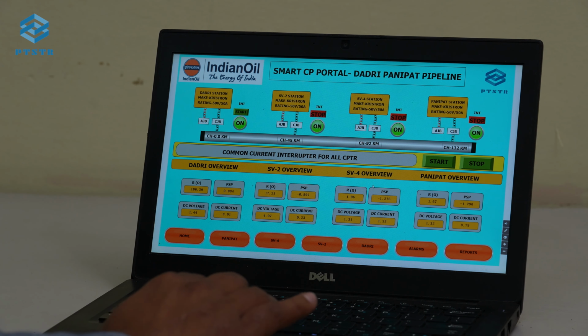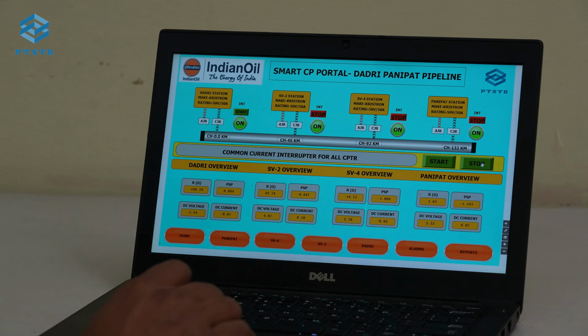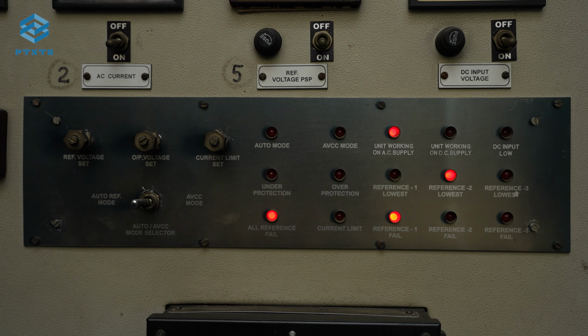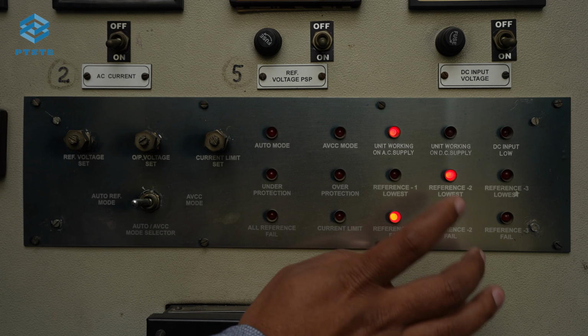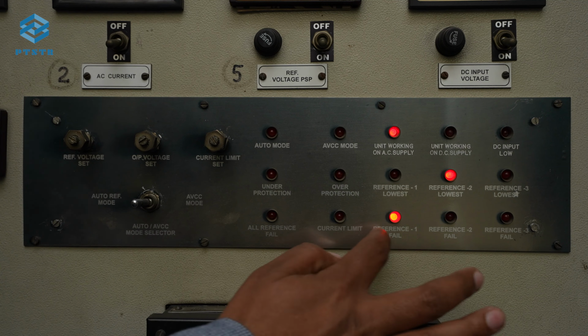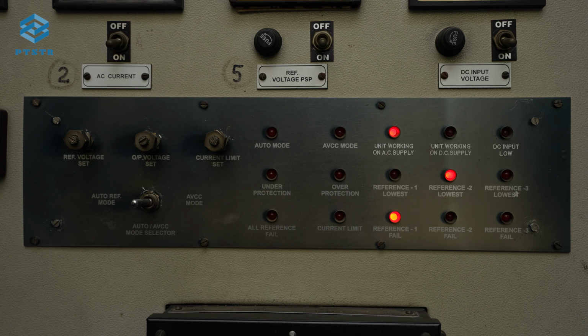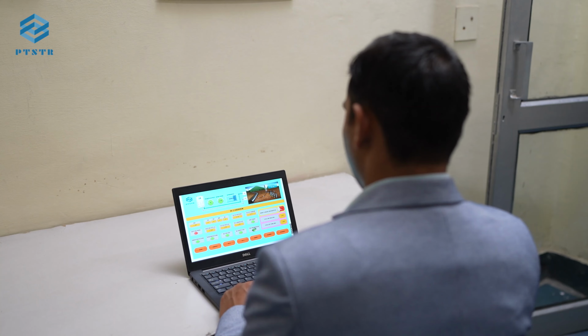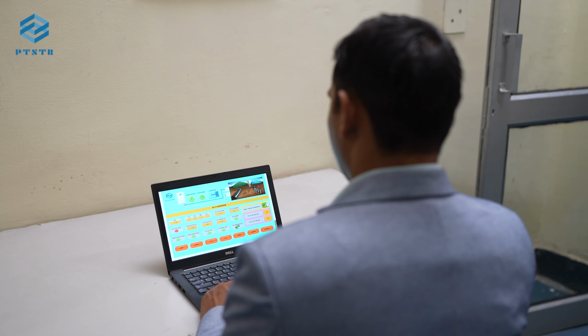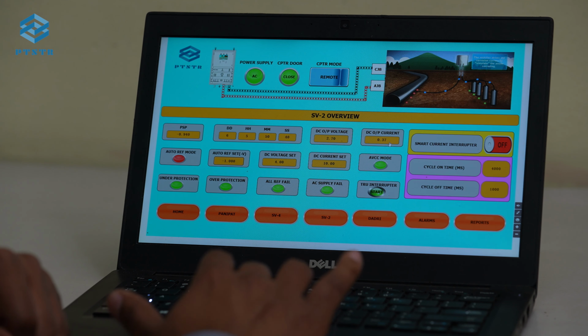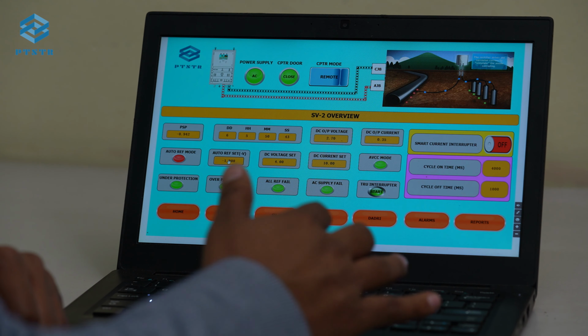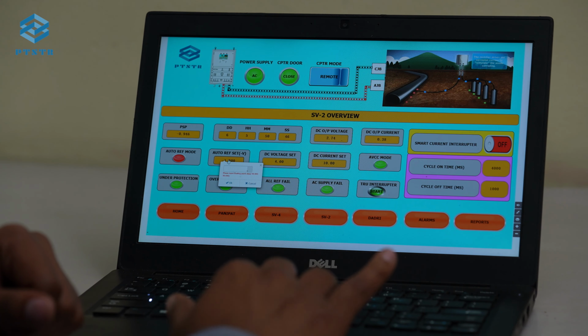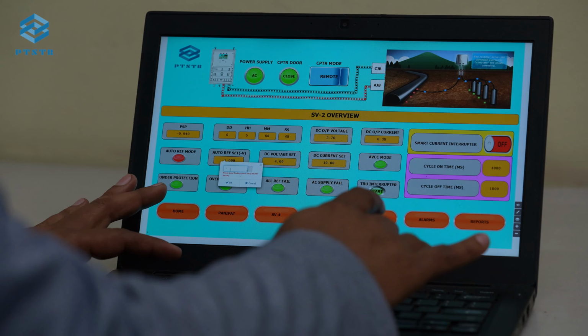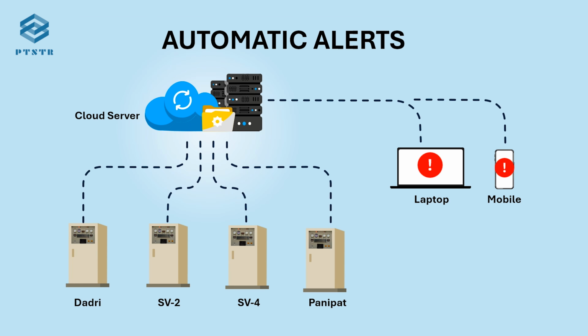This smart IoT-based system includes protections, monitoring and alert for CP overprotection, CP underprotection, reference fail, power failure, DC resistance monitoring, CP door open, R meter etc. or many more customizable as per requirement. With the implementation of smart IoT-enabled CPTRUs, this process is now seamless. Using a laptop or mobile device, a technician can remotely configure all CP parameters and interrupters within seconds, eliminating the need for on-site visits. The system can even trigger automatic alarms and alerts through mobile and email.